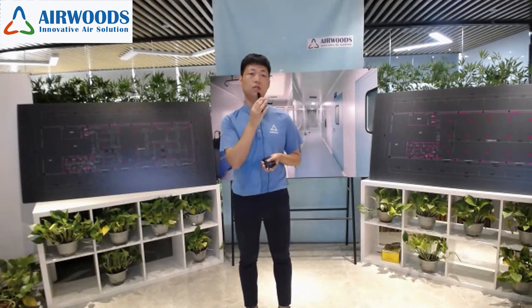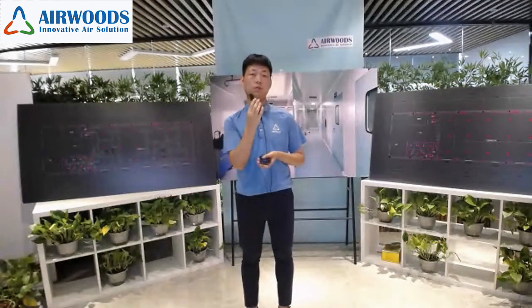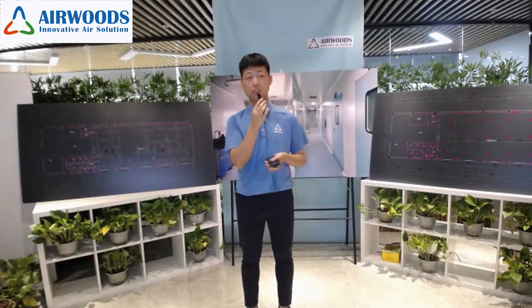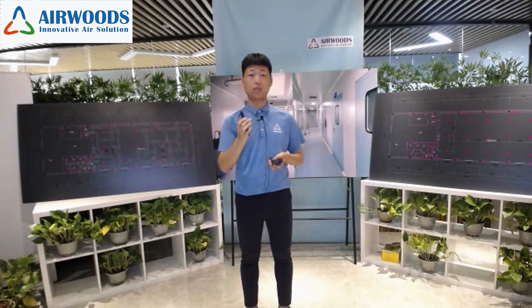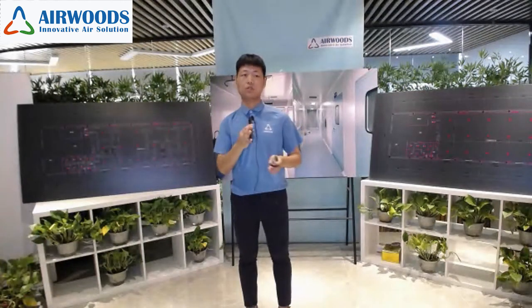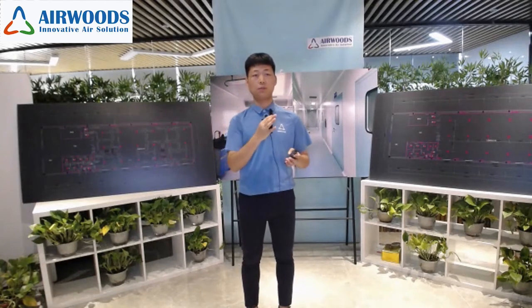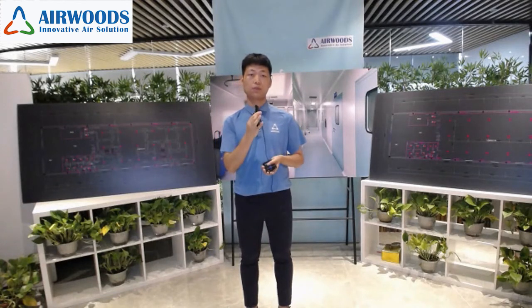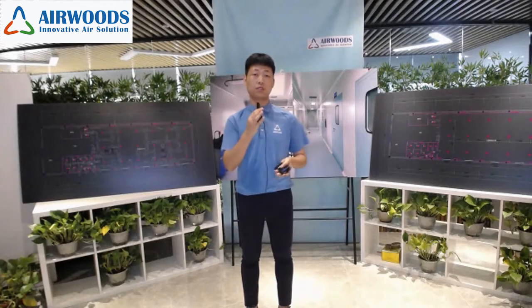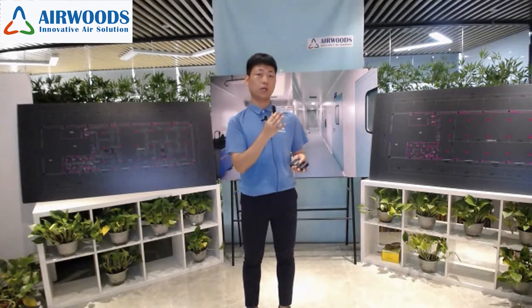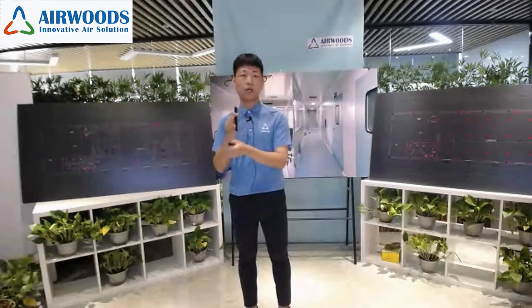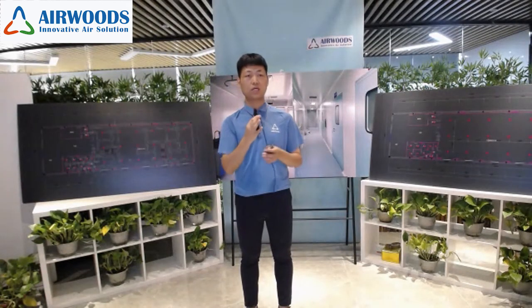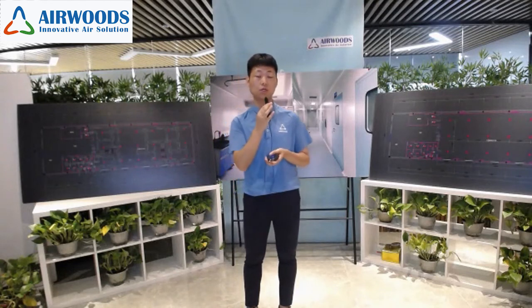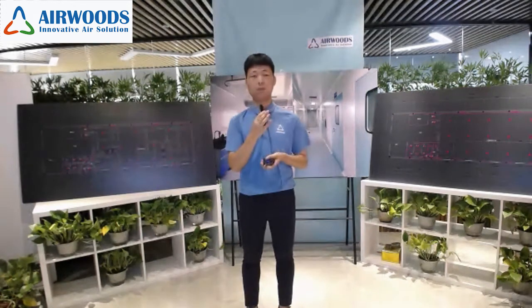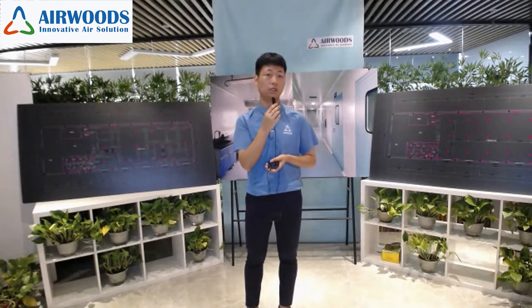Okay. Actually, the temperature and humidity control and the pressure control do not conflict. They are separate controls, because the pressure comes from the supply air. Meanwhile, we cool or heat the supply air to the target humidity and temperature with the PLC controller. We can set the required humidity, temperature and pressure values on the PLC controller. So they are adjusted and controlled automatically by the PLC controller. So it can be managed easily. Don't worry about it. Okay.